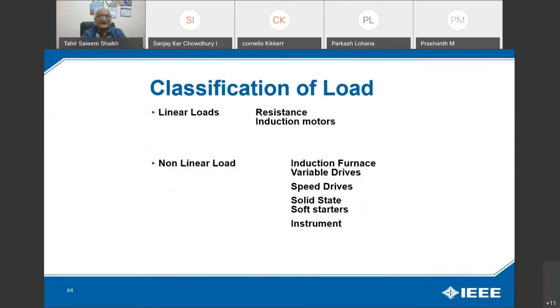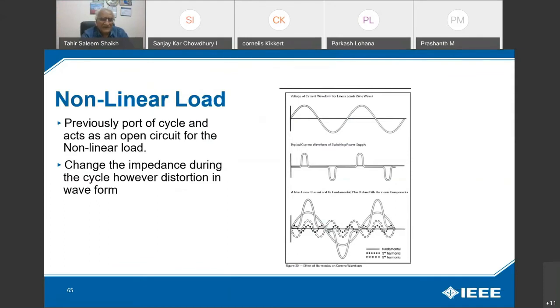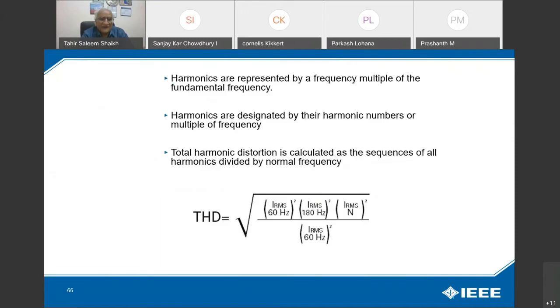Now, what are the linear loads? Resistance and induction motors. Non-linear loads may be induction furnaces, variable speed drives, solid state soft starters, instrumentation, computers, and so on. These are the non-linear loads which disturb the power factor. This is an example where the base frequency is taken as 50 Hz. Harmonics are multiples of the fundamental frequency and are designated by harmonic numbers. Total harmonic distortion is calculated as the square root of the sum of squares of all harmonics divided by the fundamental. This gives you the formula over here.